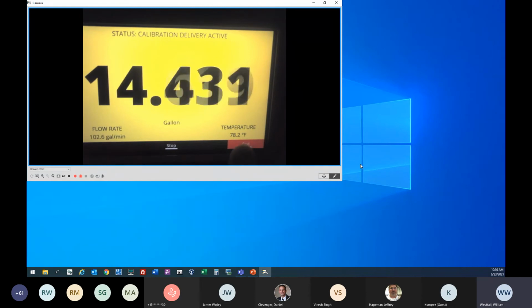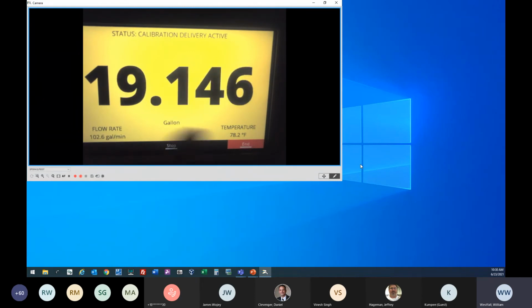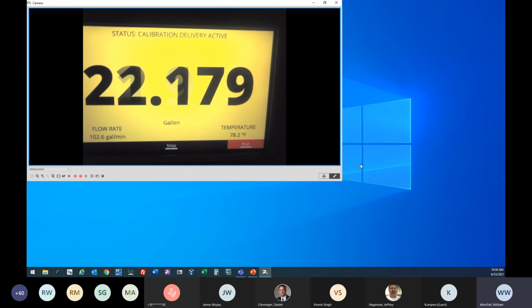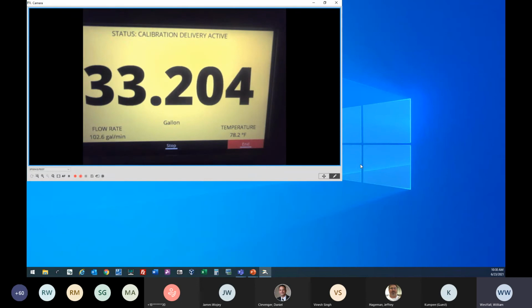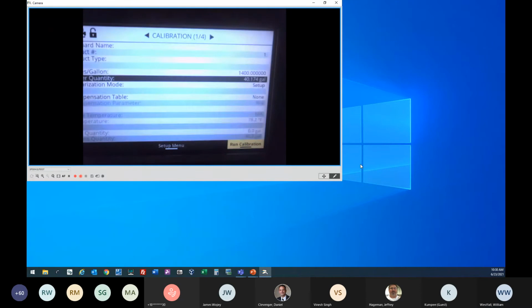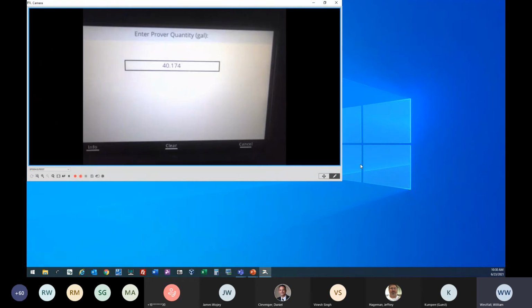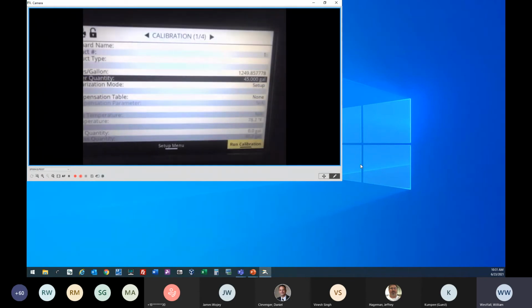It's given us our flow rate. We're getting our temperature. Once we're done with this calibration, and you'll see calibration delivery active up at the top, once we have filled up our prover, all we have to do is hit the button right below end. It'll take us right to our prover quantity. In order to enter that, all we have to do is hit the OK key. Let's say it was a 45 gallon prover, so you put in 45 gallons. That's how much is in our prover. We actually ran 45 gallons into the prover, so just hit OK.